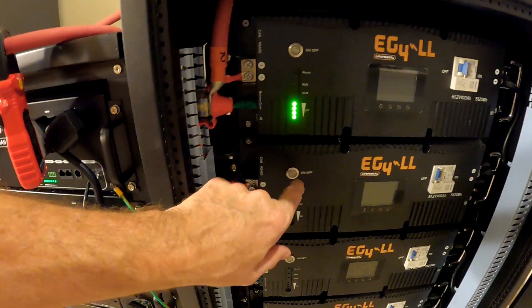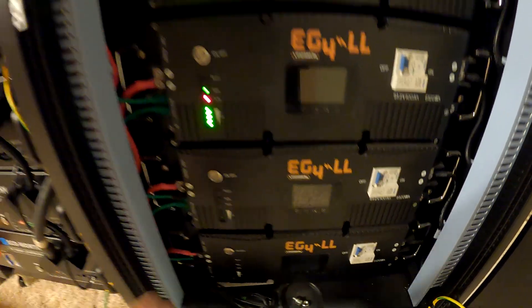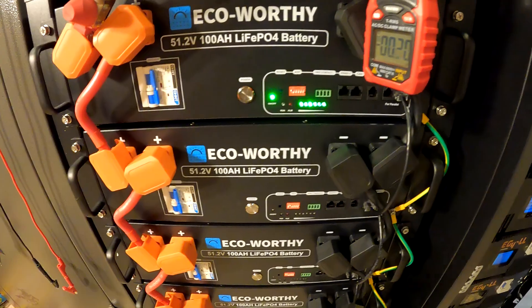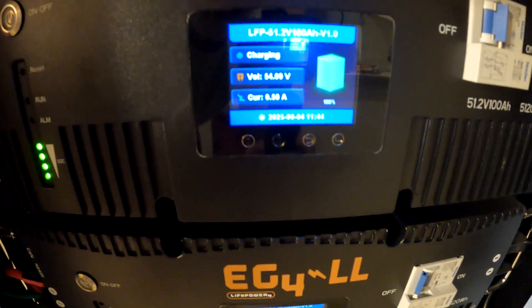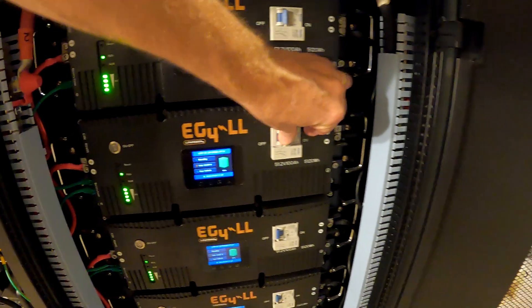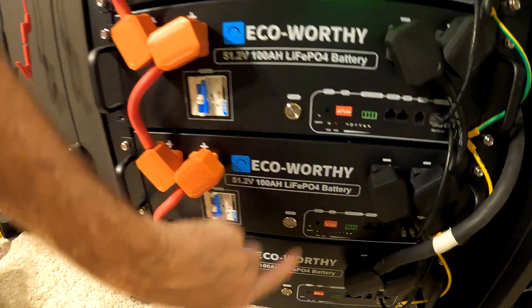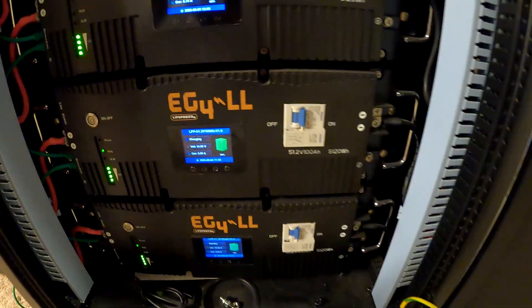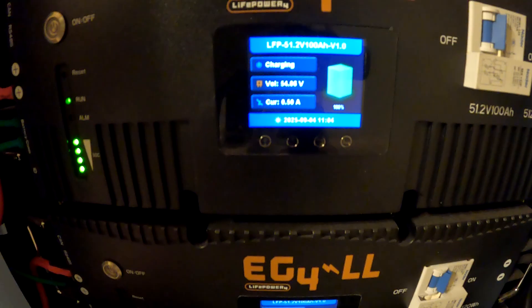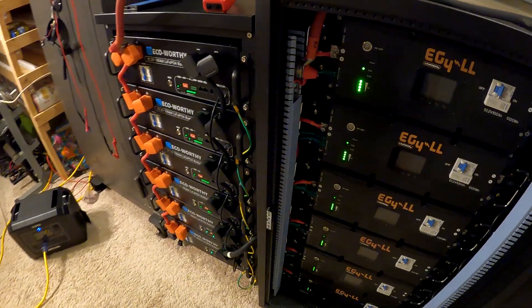Turning on the remaining batteries one at a time, checking for current flow — not much, around one amp or less than an amp as each one comes online. After all batteries are activated, the reading settles to about half an amp.